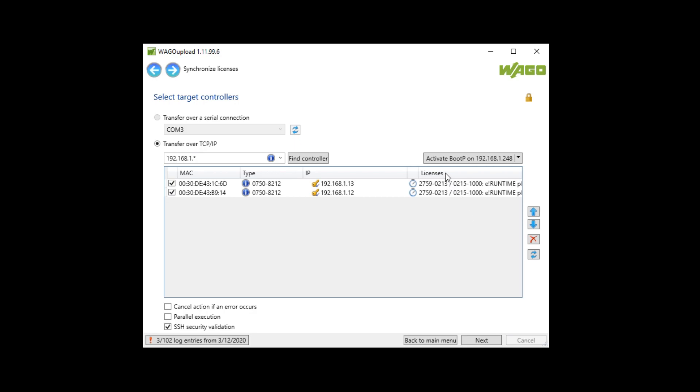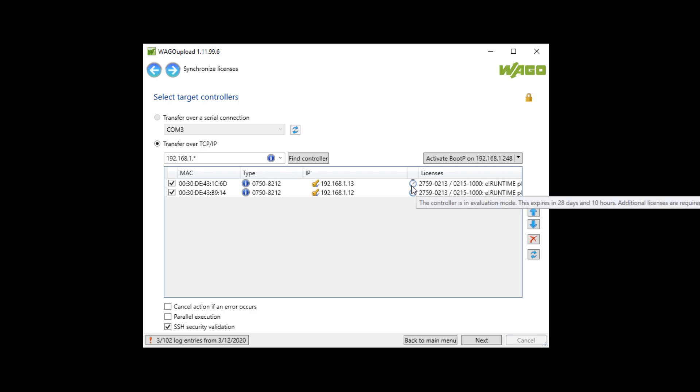In the tab licenses I see that on both controllers is a license e-runtime. A clock picture shows me that the controllers are in a 30 days evaluation mode. That means there is an application installed which needs a license but the license is not installed now.